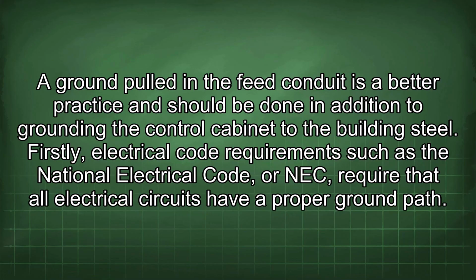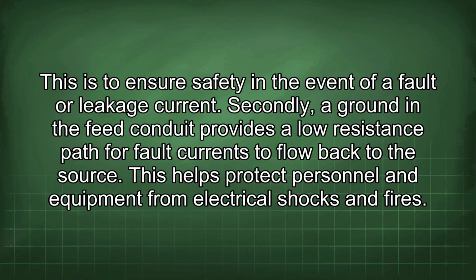Ground pulled in the feed conduit is a better practice and should be done in addition to grounding the control cabinet to the building steel. Firstly, electrical code requirements such as the National Electrical Code, or NEC, require that all electrical circuits have a proper ground path. This is to ensure safety in the event of a fault or leakage current. Secondly, a ground in the feed conduit provides a low resistance path for fault currents to flow back to the source. This helps protect personnel and equipment from electrical shocks and fires.